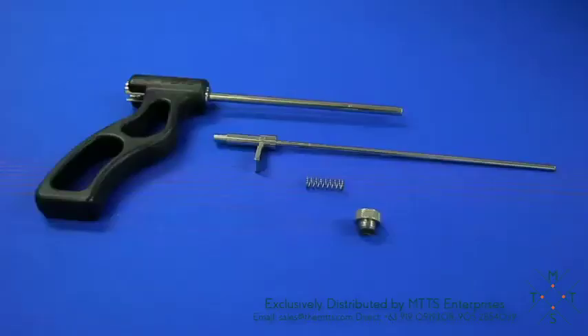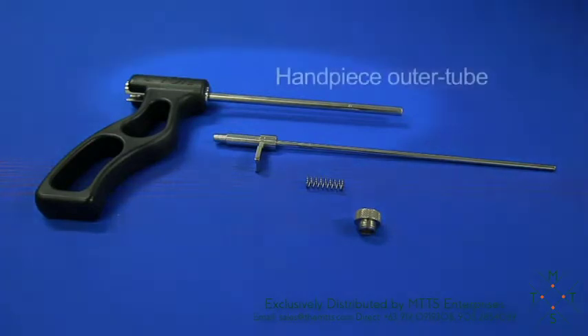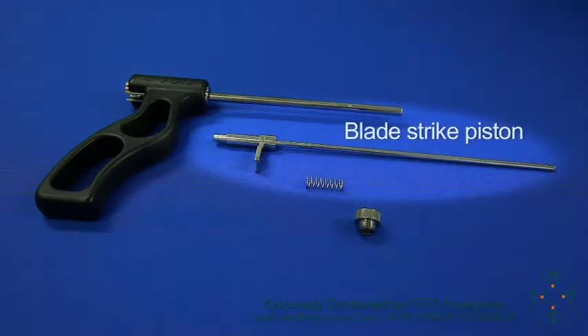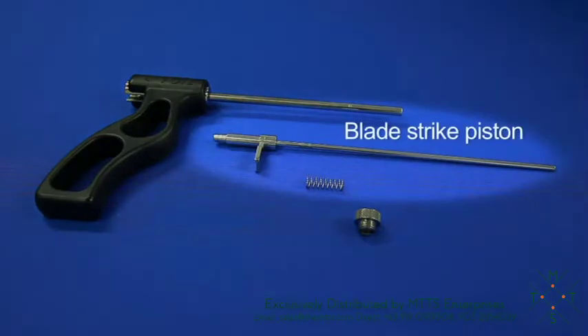It has a pistol grip design to enable a comfortable feel for both left and right-handed use and also for above and below hand approach techniques. The handpiece outer tube acts as a housing for the blade striking piston and for securing the capsule. The blade strike piston has a cannula from front to back and a trigger for easy blade activation.